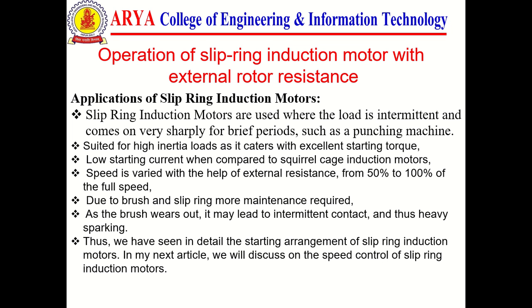Due to brushes and slip rings, these motors require more maintenance. This is the disadvantage of the slip ring induction motor. As the brush wears out, it may lead to intermittent contact and thus heavy sparking. So these are the main disadvantages. Thus we have seen in detail the starting arrangement of slip ring induction motors.